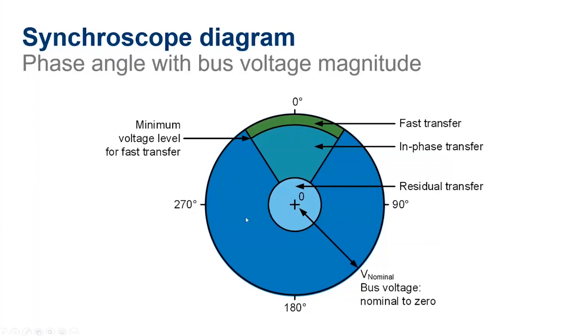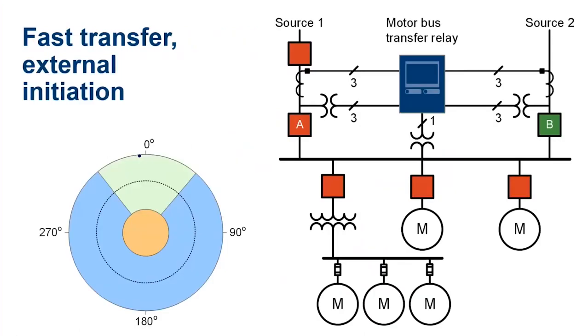Then we have this blue region here where the phase angle is either too big and the magnitude might not be low enough to do a residual transfer yet. And finally, when the voltage magnitude falls within this inner circle, that's where we would start a residual transfer. And so we have settings for most of these to define all of these regions. I'll go a little bit through those during the presentation. Okay, so the first of the transfers I'm going to consider is the fast transfer. In a fast transfer, we need two sources that are relatively close to each other.